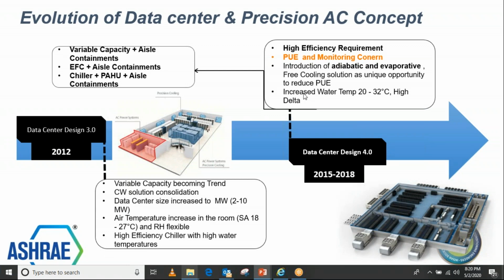And in 2015 to 18, there was a big revolution which happened in the industry in terms of the temperature. In India itself, we designed many data centers which had the water temperature going up to 20/27. We designed many data centers with chilled water temperature 20/27. So imagine from 7/12, which used to be in 2005, 7, 8. Imagine that kind of 2007, 8 year to now in 2018, or even now you are going around 20/27 or 20/32 kind of water temperature in the chiller.